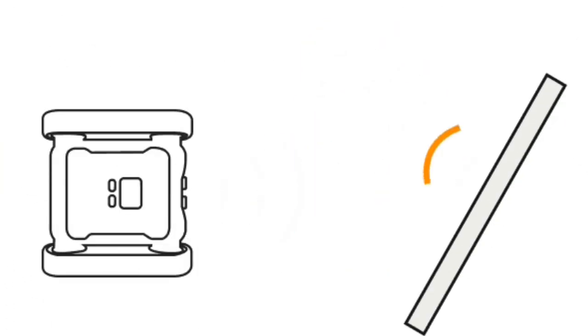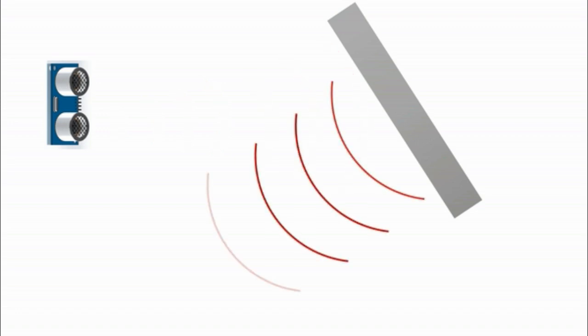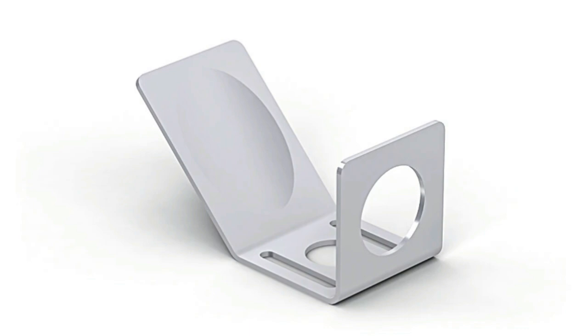The ultrasonic waves can be deflected by another object. This object must have a hard, flat surface that relays the signal well. Care should be taken to ensure that only one deflection is used, as multiple deflections result in a significant decrease in sound wave range. To ensure that no large debris falls onto the active surface, a baffle plate can be used.